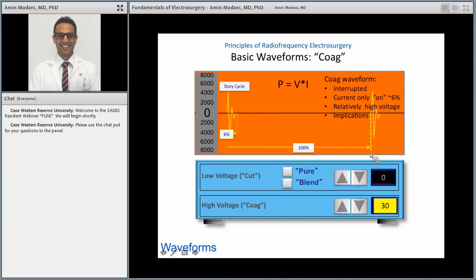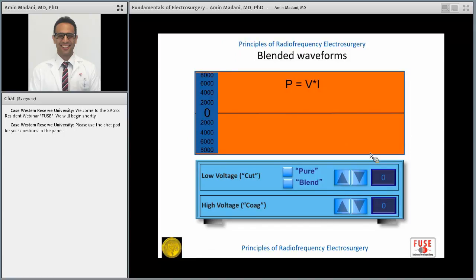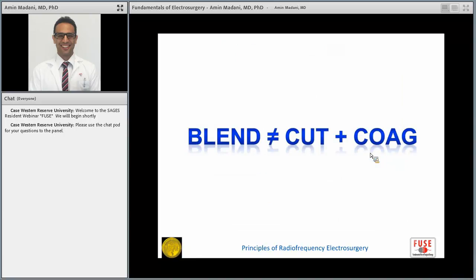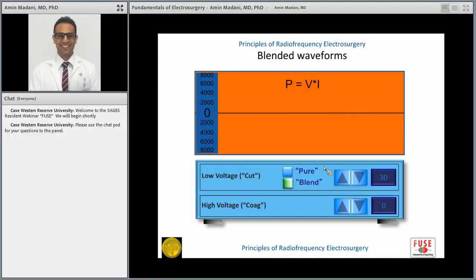And what about blend? We often see this function on the ESUs. It's very similar, but essentially it's a spectrum. If we put blend on 30, the same amount of power again, and we deliver the current, now it's about 50% of the time. So it's basically a spectrum. On one end of the spectrum, you have cut, which is 100% duty cycle, and on the other end, you have coag, which is 6% duty cycle. But you also have settings in between if you want to customize things intraoperatively.